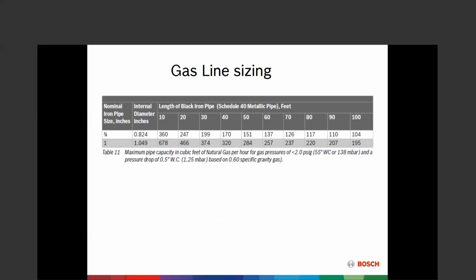Gas line sizing, big deal. We've got to get enough fuel to these things, right? We have to get enough fuel. You see this chart here is our very conservative chart. This is one that only allows for a 1/2 inch pressure drop. That's all it allows for. So with this one, we're going to start with 3/4 inch. It's the smallest we're going to talk about, a 3/4 inch gas line. But I said you can use 1/2 inch. Yes, you can use 1/2 inch.